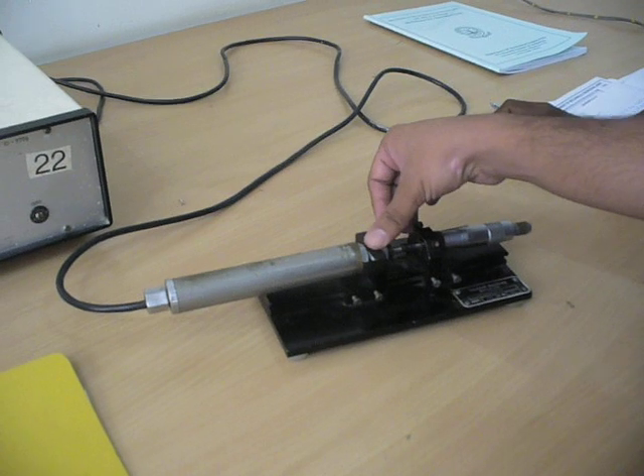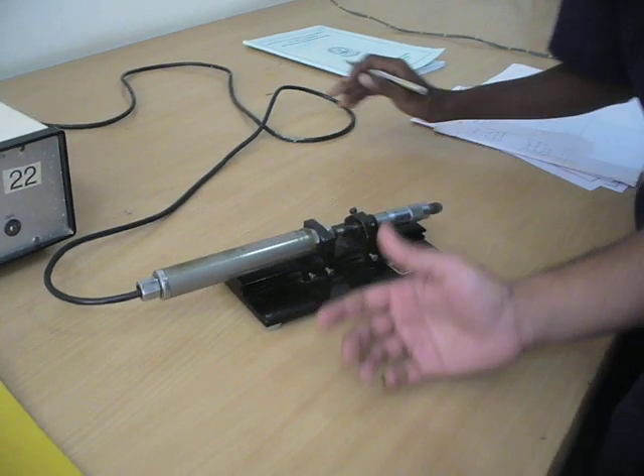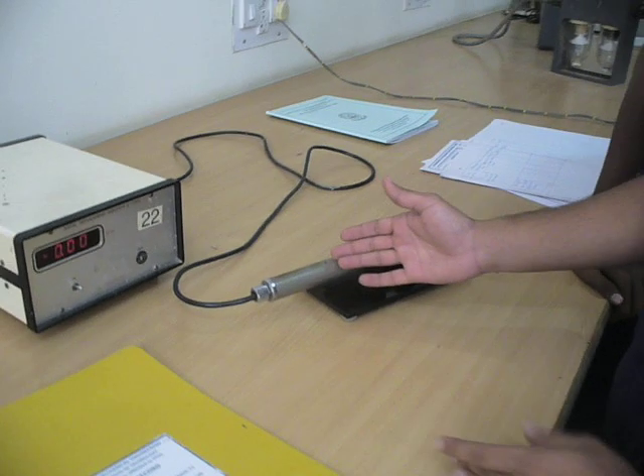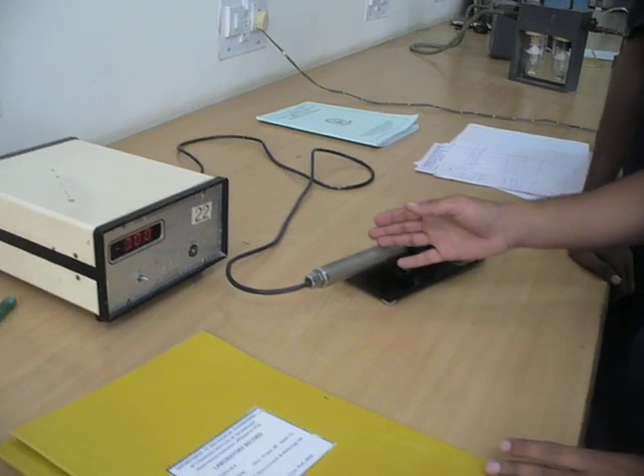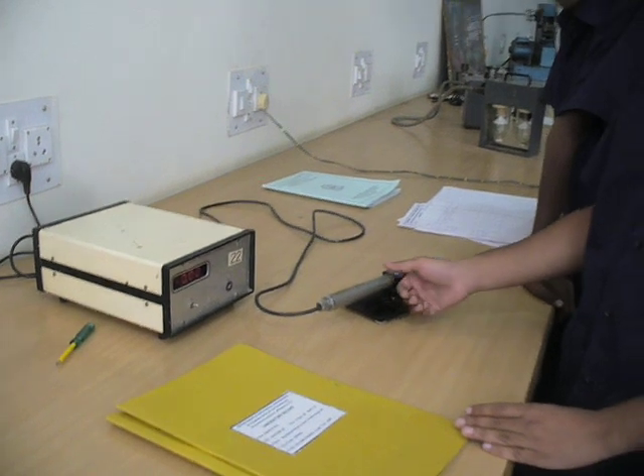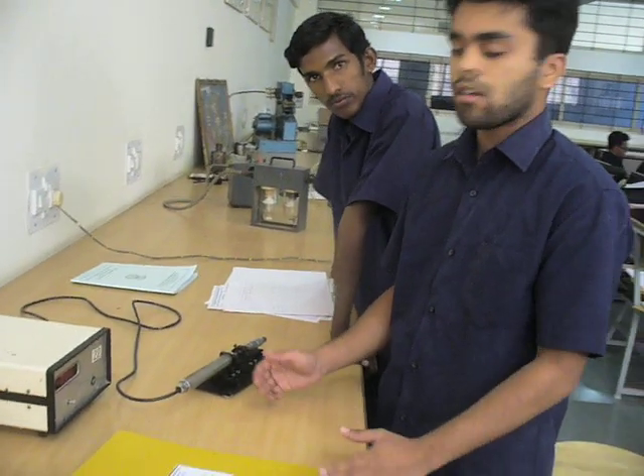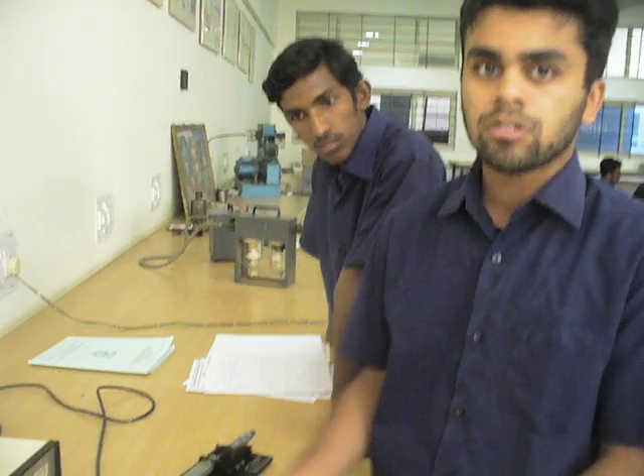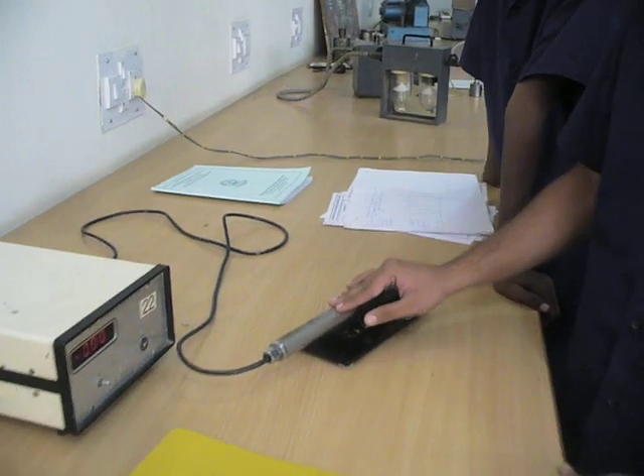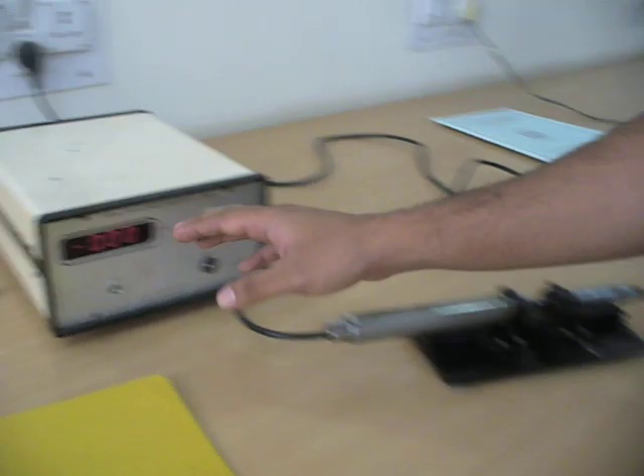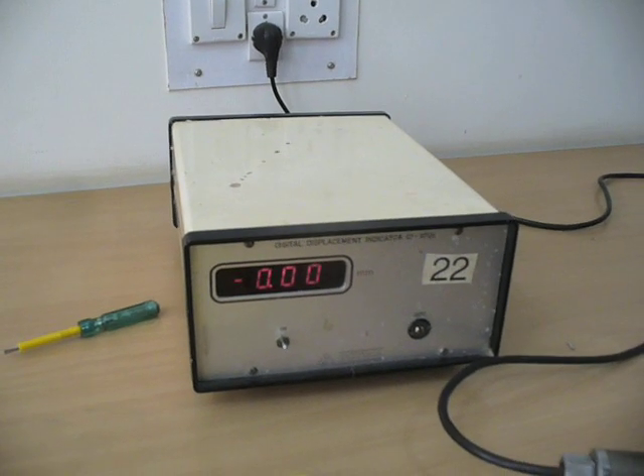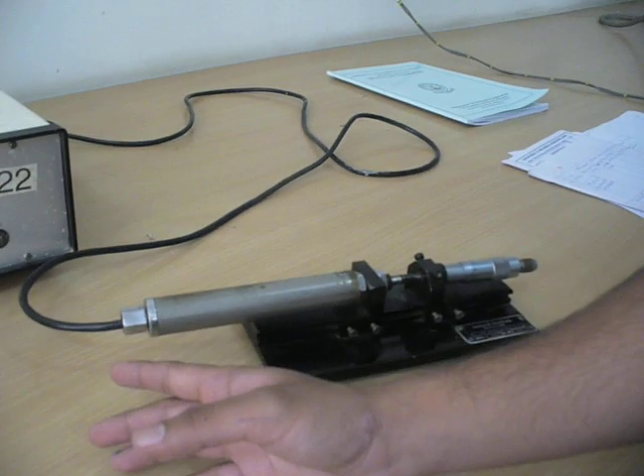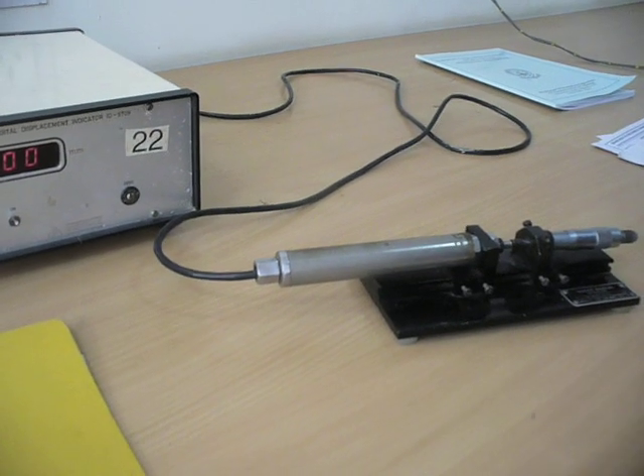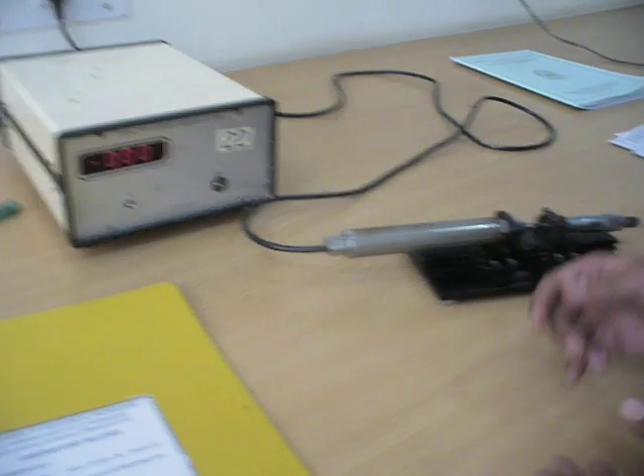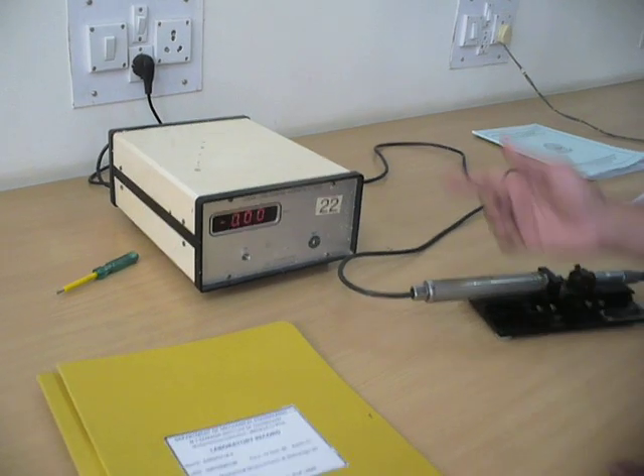So how the LVDT works is there is one primary coil and two secondary coils, and the two secondary coils are connected in opposition to each other. So the output voltage is determined by the position of the core inside the LVDT. When there is a displacement of the core to either the left side of the null or the right side of the null, the reading is shown here. Initially the core is at null position, so the reading over here is 0. When there is a displacement in the micrometer, the core moves to one side, and thus an extra voltage is induced in one of the secondary coils. This induces a voltage which is shown over here.